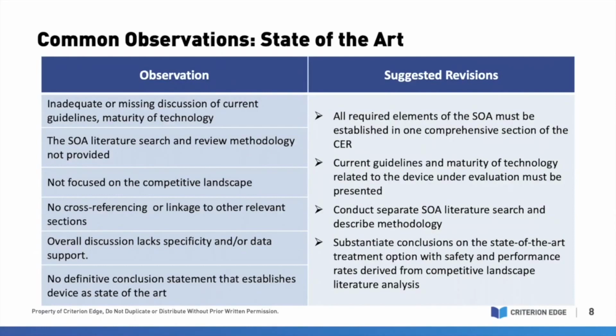Presented here are some common observations noted in past CERs that we've updated to MDR compliance, and a few suggested revisions you should consider. For example, inadequate or missing discussion of current guidelines and maturity of technology. Another gap we commonly encounter is that the state-of-the-art literature search and review methodology is not provided at all.